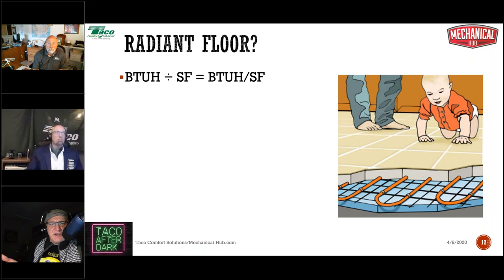There's an asterisk here. In kitchens, you have cabinet space. You put tubing under cabinet space, it keeps the cabinets nice and warm, but in terms of heating the room, it simply doesn't count. You can't rely upon it. Same thing in bathrooms. If you put tubing under the vanity and under the bathtub, it's nice. It's nice to have a warm bathtub. It's one of the cool things you can do with radiant. It simply doesn't count in terms of effective radiant floor space. So you'd have to back that stuff out in doing those calculations.